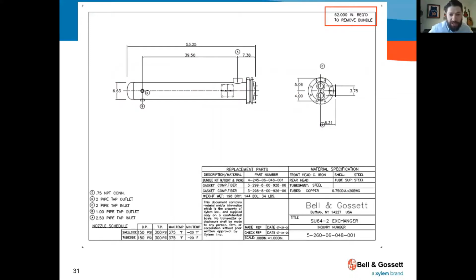So this is your typical submittal sheet you're going to get with every heat exchanger. It doesn't say your clearance in the I&O manual, but it's going to say it on your submittal. So I boxed it there in the top right corner, 52 inches required. Now, as you see, this whole unit is only 53 inches, and this is a pretty small stock unit. It's about 53 inches long. So you do need 52 inches to pull out that tube bundle, right? That tube runs pretty much the full length of the unit.